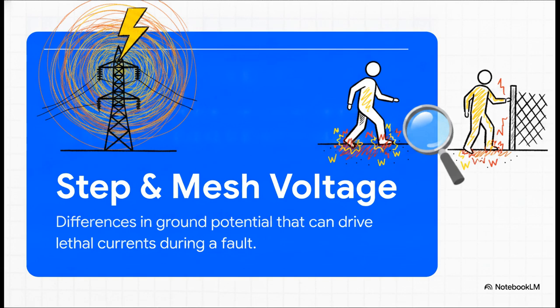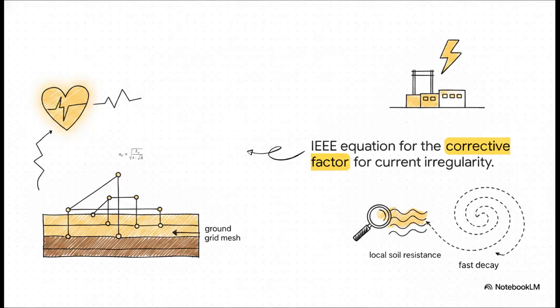Step voltage is the dangerous difference in electrical potential between your 2 feet when you take a step. Mesh voltage is the potential difference between a grounded piece of equipment you might be touching and the ground right beneath your feet. Without proper engineering, just walking through a substation during a fault could electrocute you. So, to protect human lives, engineers use incredibly dense math, like this IEEE geometric equation, which is used to calculate corrective factors for current irregularity. They literally have to calculate exactly how a fault current will split, how fast it's going to decay, the specific resistance of the local soil, and exactly how that energy will travel through the earth. They map out the exact geometry of the substation just to ensure that the mesh and step voltages never, ever exceed what a human heart can withstand.